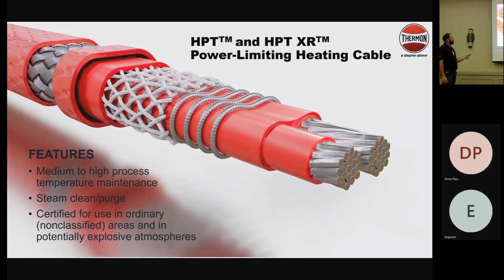This cable right here, I worked in R&D for 9 years before I came over into the bundle group and did return material analysis. I saw some HPT come back, but it was always off a pipe - somebody was doing maintenance, they'd rip it off not knowing what it was, and they'd tell me what happened to the heater, and I'm like, I don't know, I wasn't there. But I never saw any come back in a bundle, because it's protected by the insulation. This stuff will last - I heard somebody talk about 15 years. As long as it's dry and it's in a bundle, it'll last as long as the tubing lasts. So it's pretty reliable.